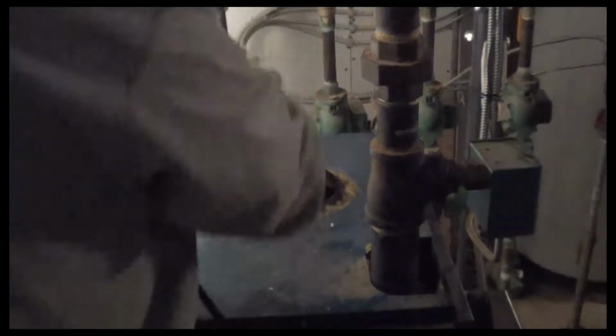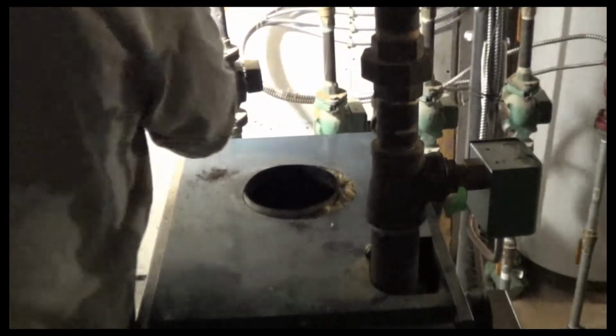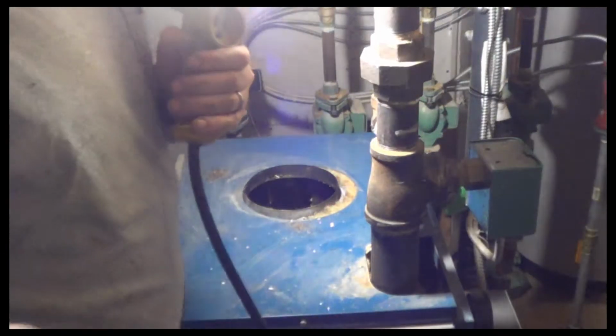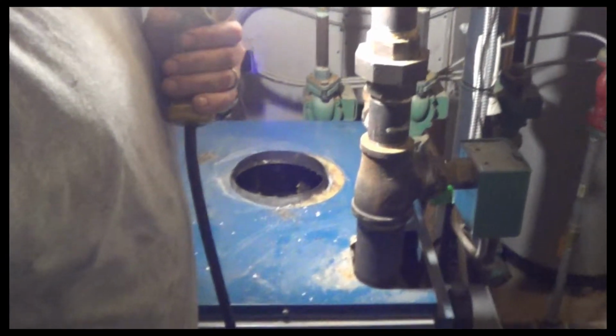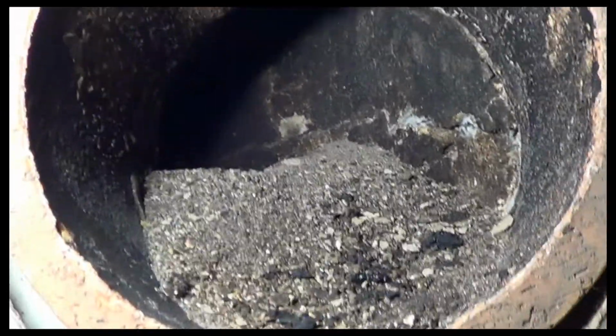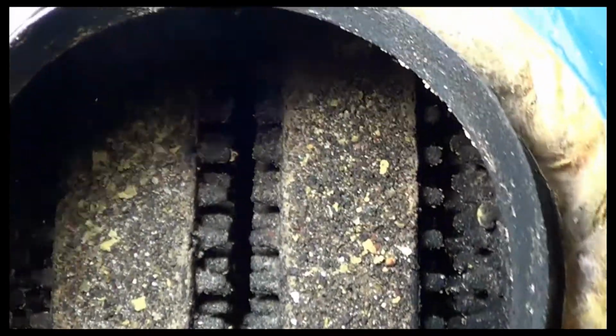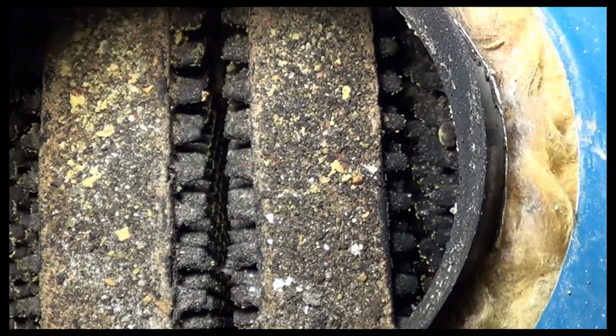I'm going to inspect the chimney base. I got to show you the chimney base. This is a great example why we check chimney bases. Grab my tripod out of there. You can see that. That's oil for you. That's almost totally plugged. Again, this is a new customer, my first time cleaning this for them. And that chimney base is plugged. That's the inside of the heat exchanger. We're going to get right down inside that heat exchanger.